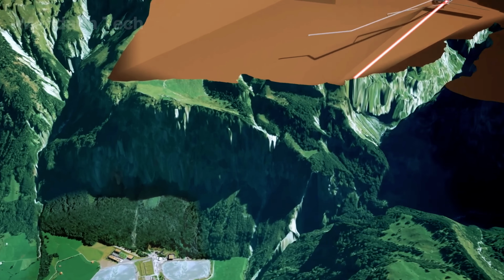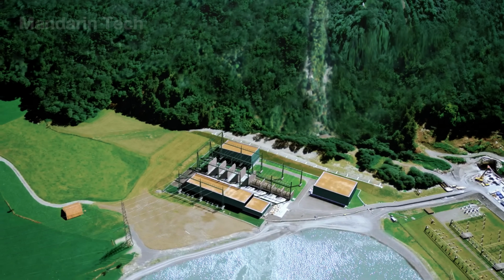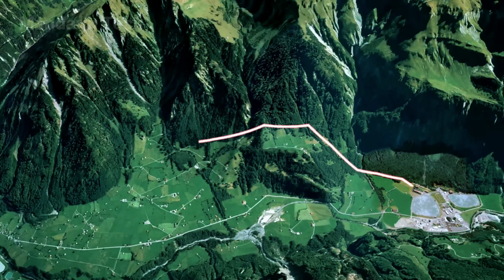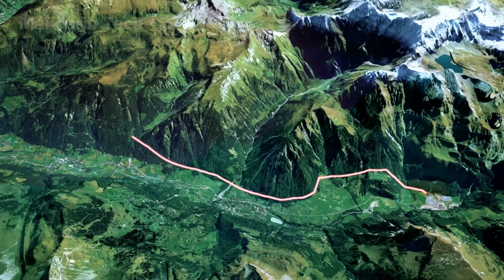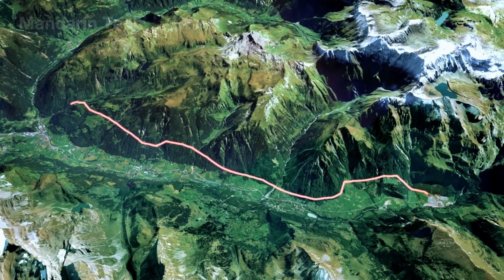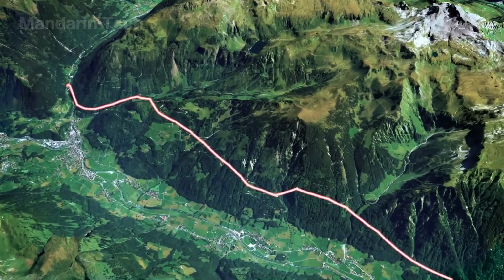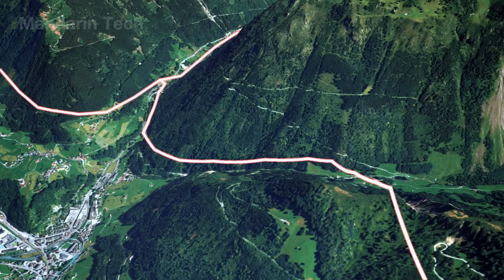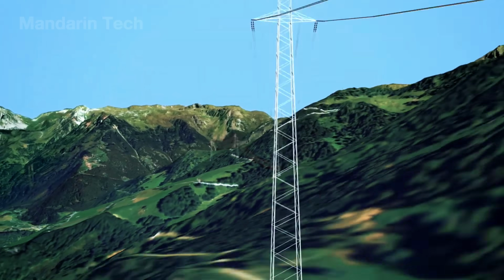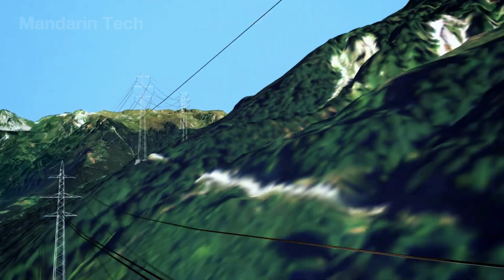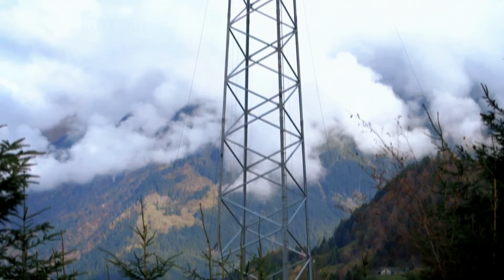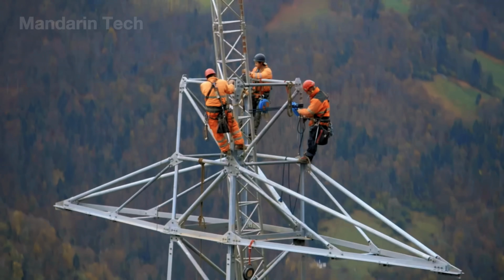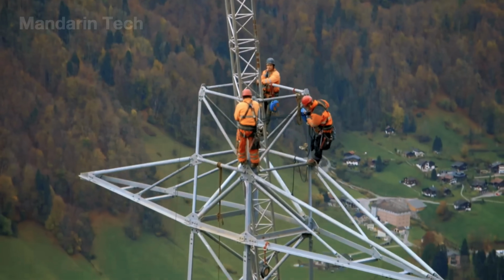To connect the power plant to the grid, high-voltage power cables were routed through an access tunnel to the substation in Tierfed. From there, a new 380 kilovolt transmission line was built across the Linthal Valley. This 17-kilometer line became part of Switzerland's extra high-voltage power network. To construct it, a total of 53 new transmission towers were erected. Some of these towers reach heights of up to 89 meters, making the construction process extremely complex.